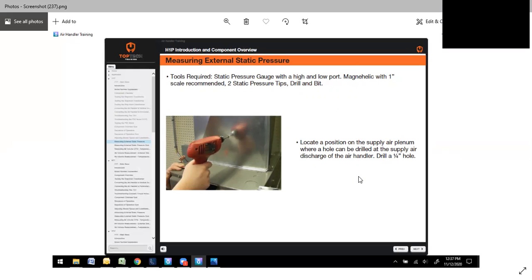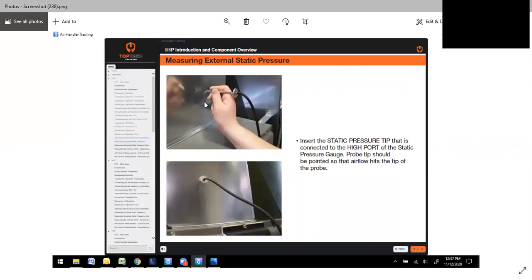Locate a position on the supply air plenum where a hole can be drilled. Drill a 1/4-inch hole. You have your little pitot tubes here, which are specifically for reading static pressure. Insert the static pressure tip that is connected to the high port of your dual manometer, the positive side of your digital manometer. The probe tip should be pointed so the airflow hits the tip of the probe. That will have a little effect on that. So that's going to test our high side.